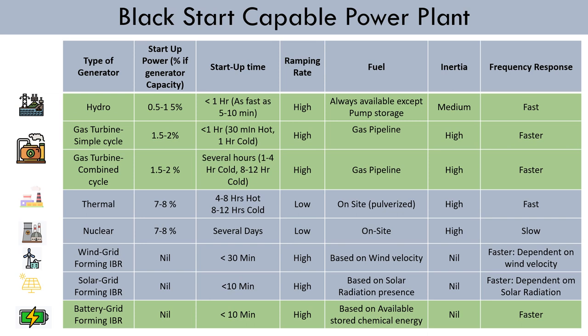Wind and solar energy power plants are not commonly utilized as black start capable power plants for several reasons. Firstly, their intermittent nature relies on weather conditions, making them unable to generate electricity during a blackout without an external power source. Secondly, these power plants lack the inherent inertia provided by traditional synchronous generators, which is crucial for stabilizing grid frequency during black start operations. Additionally, wind and solar power plants have limited on-site energy storage capacity, and implementing the scale and duration of storage required for black start capability can be challenging and costly. Lastly, these power plants require a stable grid connection to operate efficiently, making it difficult for them to independently start up and synchronize with the grid during a blackout.